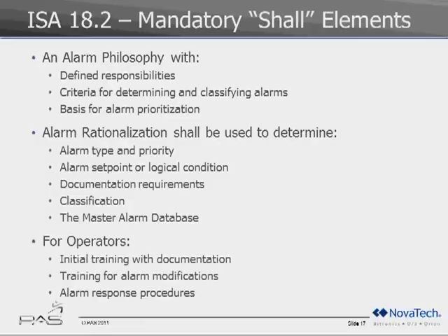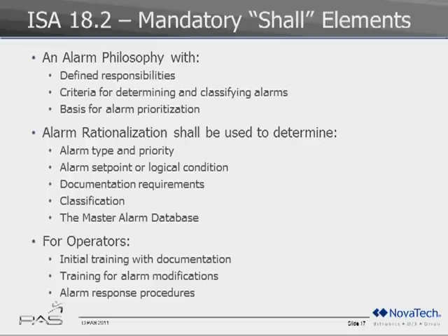The mandatory shall elements of 18.2 start with an alarm philosophy — defining responsibilities, criteria for creating alarms, and the basis for a prioritization system. There may be three or four alarm priorities, all of which must be defined in a philosophy document. The heavy lifting really comes in alarm rationalization, where you go through each alarm by type and priority, determining the set point, consequences, cause, and corrective actions so that when the alarm goes off, the operator knows exactly what to do.